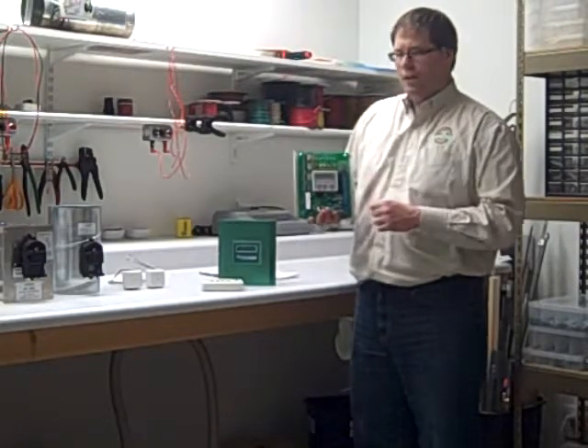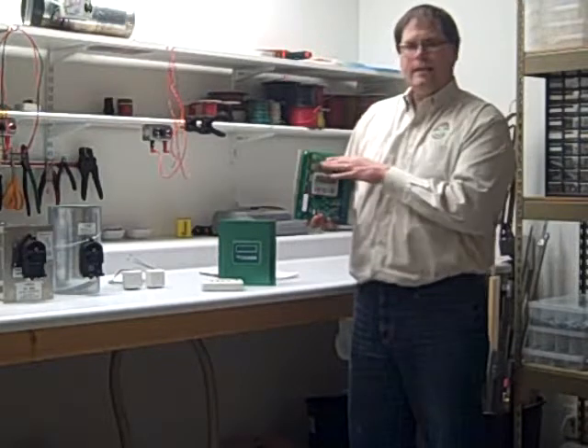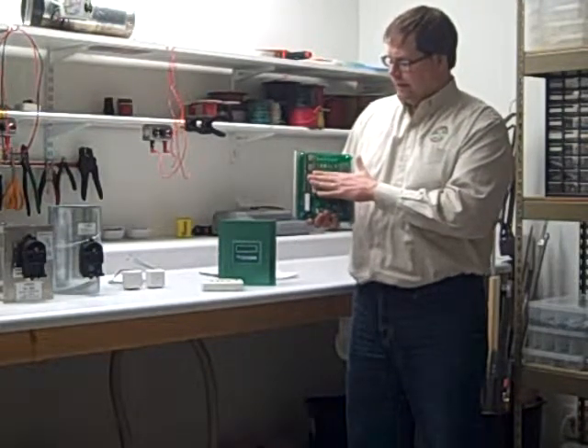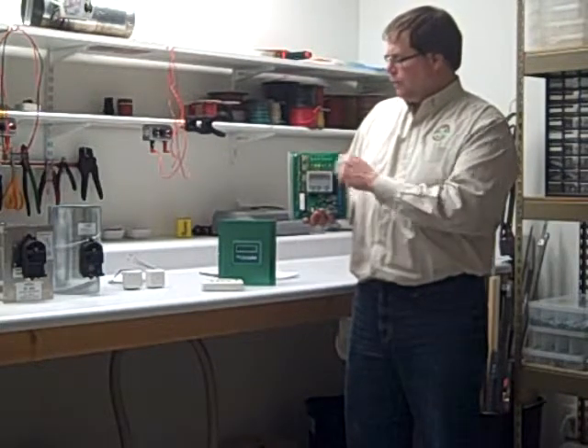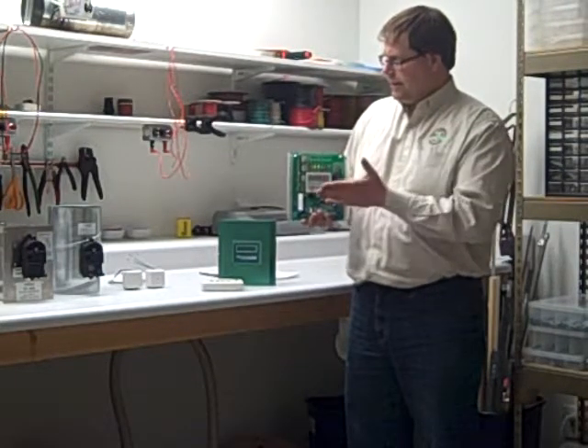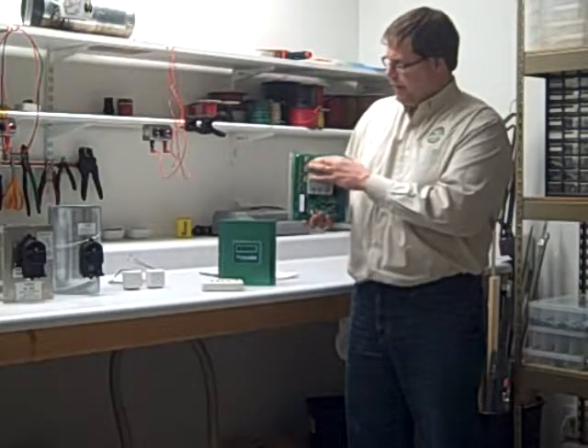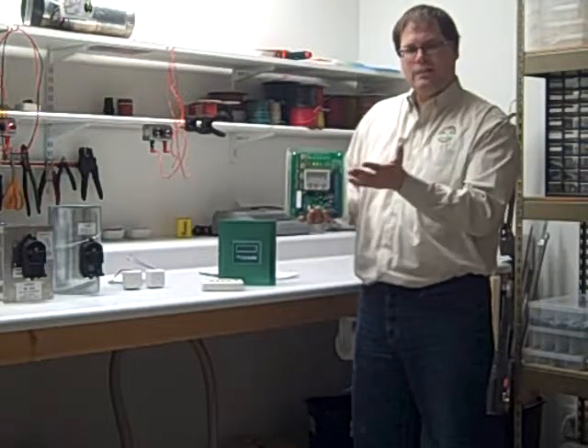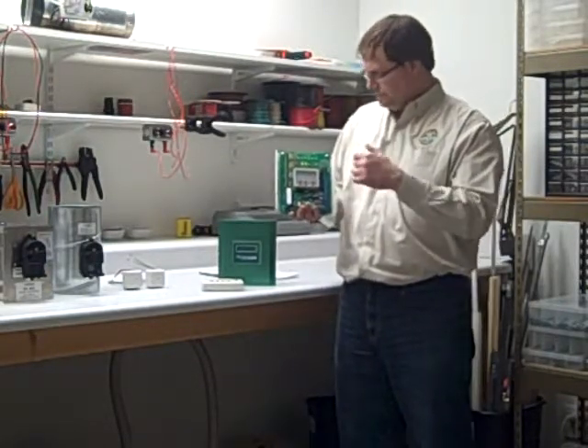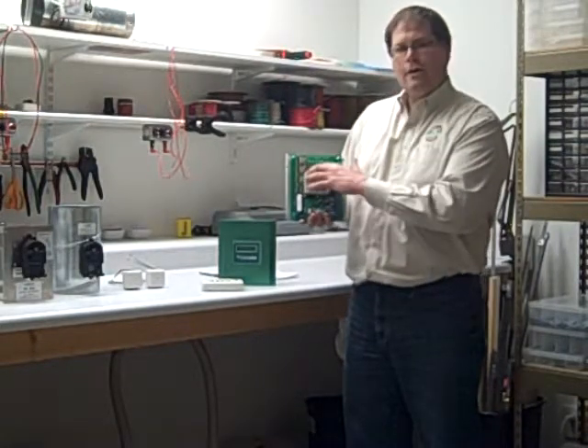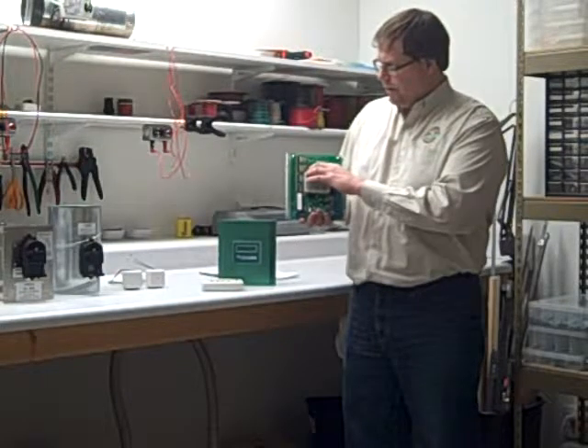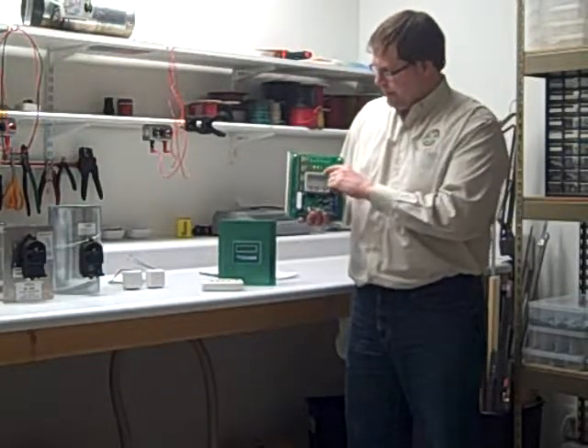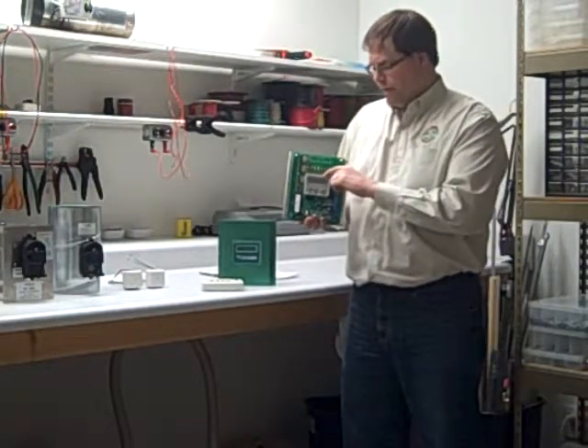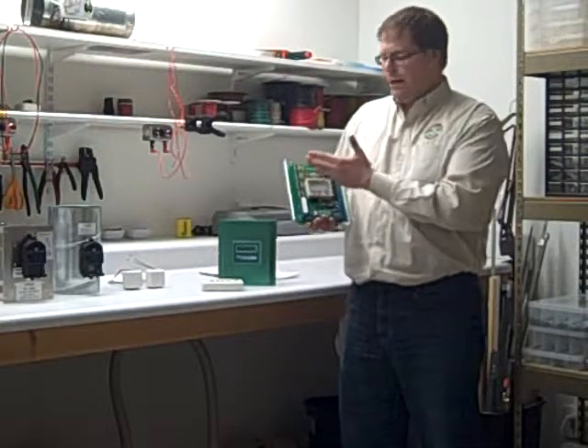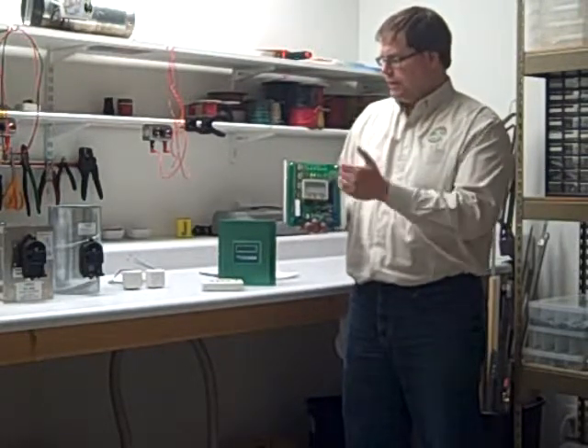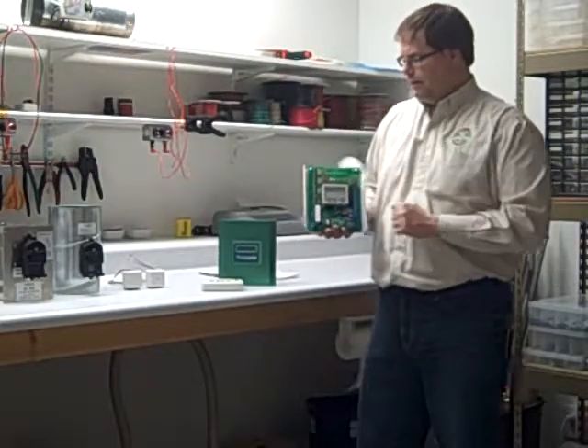And keeping with our long tradition of keeping it contractor friendly, we give you LEDs that tell you what's going on as well. Not only could you get a lot of this information through the PDM, an easy removal of the cover exposes a large number of LEDs that tell you what's going on. Everything from power to the panel, to the zone dampers, what they're doing, equipment status, which stages are calling for heating or cooling, B terminal. And then we also tell you when we're in test mode, when we're in purge mode, whether or not we've gone out on high limit, gone out low limit, we've talked about the outdoor temperature sensor, whether or not we're calling for emergency heat, and right on down the line. So pretty much anything a technician might need to troubleshoot or just get a current status, he can look at the LEDs or again go through the PDM.